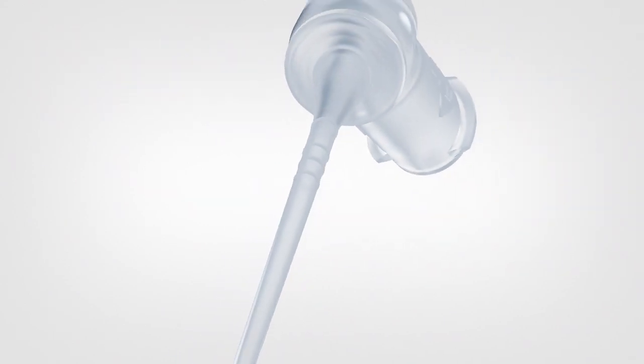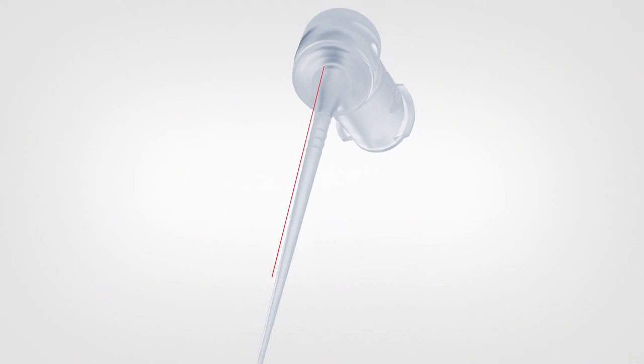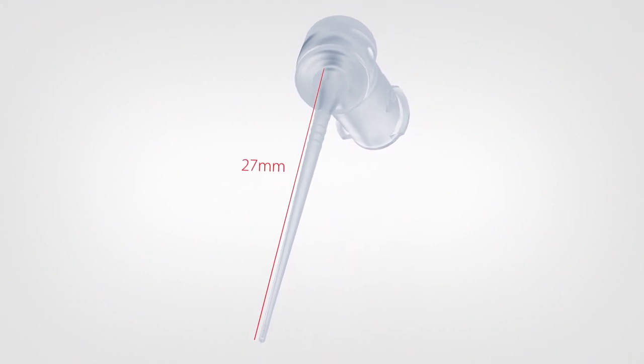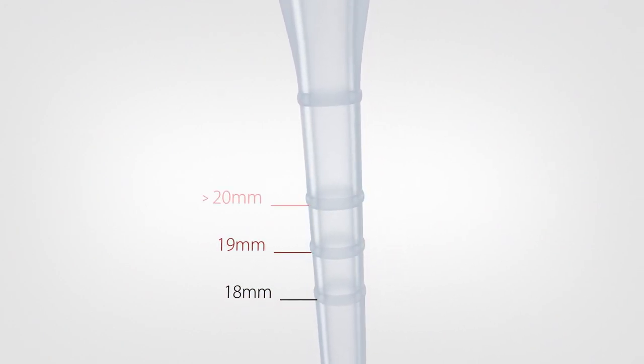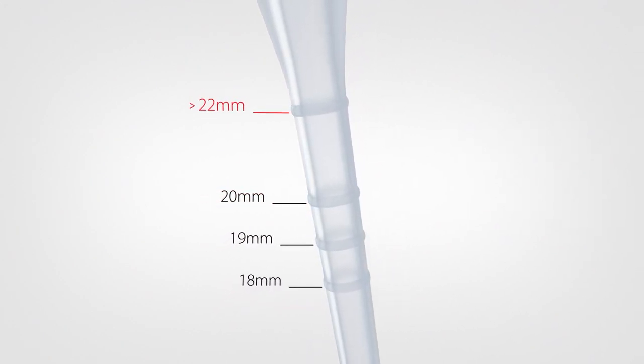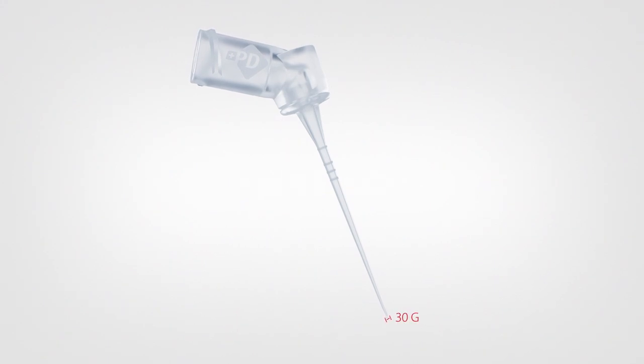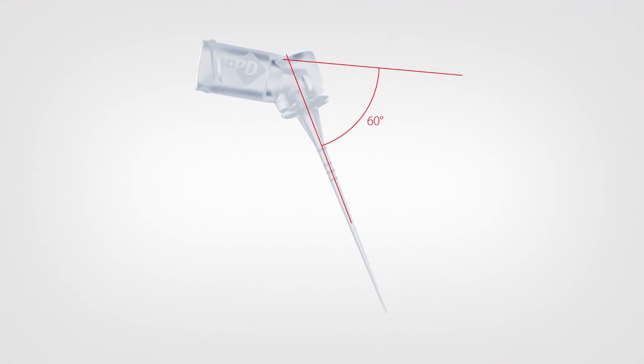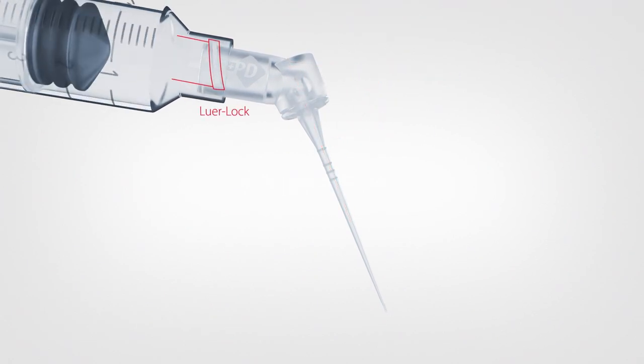The transparent Aeroflex needle is made of soft polypropylene, 27 mm long, with depth marks at 18, 19, 20, and 22 mm, 30 gauge wide at the tip, 4% taper, angulation of 60 degrees for better accessibility, and a Luer-Lock connection.